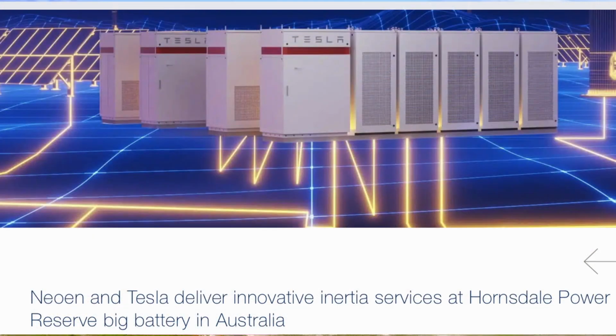We're seeing grid-forming inverters being installed at larger and larger facilities. For instance, one of the first large battery storage sites, the Hornsdale Power Reserve in South Australia, was upgraded with grid-forming capabilities in 2020. And a much larger facility in New South Wales, Australia, will also feature grid-forming inverters. The North American Electric Reliability Corporation recently published a recommendation that all future large-scale battery storage systems have grid-forming capability.